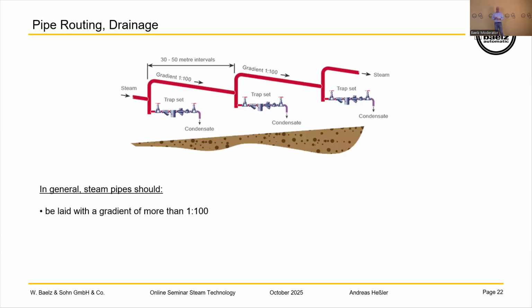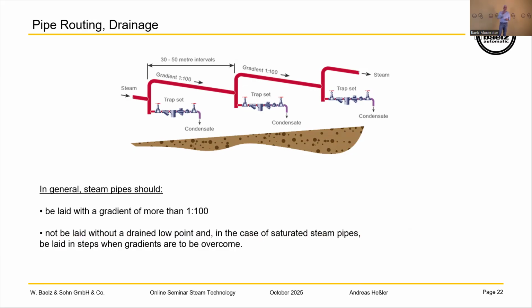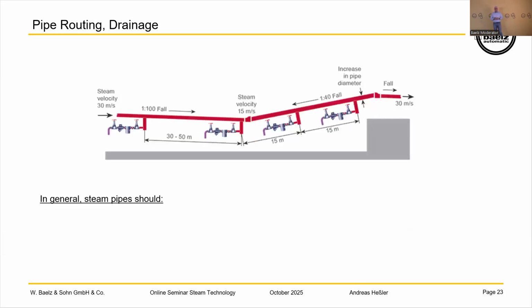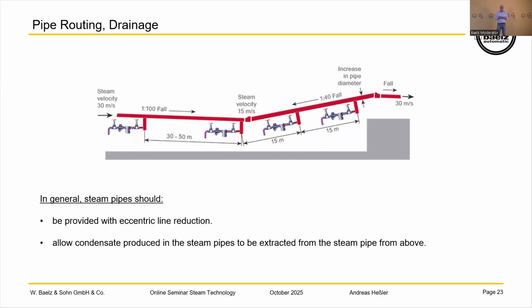If you have a slope of more than 1 to 100, the installation should be like shown in the picture, making a lowest point and a strainer there. And here I have another picture when we have some ups and downs and how they fall. It would be good, when you fall down, that the installation of the strainer is less than 30 to 50 meters. Also very important is to use an eccentric line reduction and not a concentric one. That's what the slide said. You can check it later to have it exactly. It's good information for you.